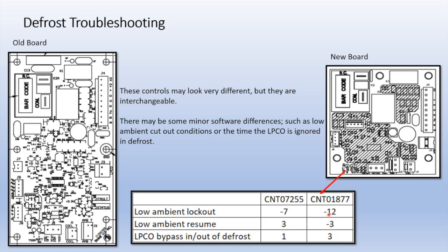The other thing it's going to do is during a defrost, that indoor coil is really cold, absorbing that heat. And without indoor heat running, you're gonna have cold air coming out of the ducts. So it tempers the air coming out of the system.